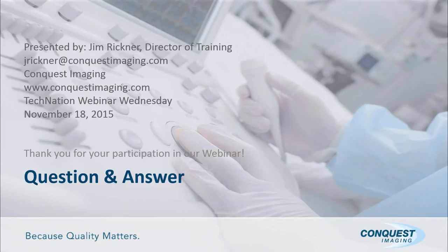All right, moving on. How can you protect the system from a software or hard drive failure? Well, that's one of the things that we absolutely recommend. Since in this case you can't download software and reload it onto the system, what we highly recommend is to make a digital image of your hard drive, a bit-for-bit image, and have that located in a safe spot. If your hard drive does fail, or if the software does get corrupted, you're simply able to plug in a hard drive with a digital copy and bring your system right back up to a functional state.